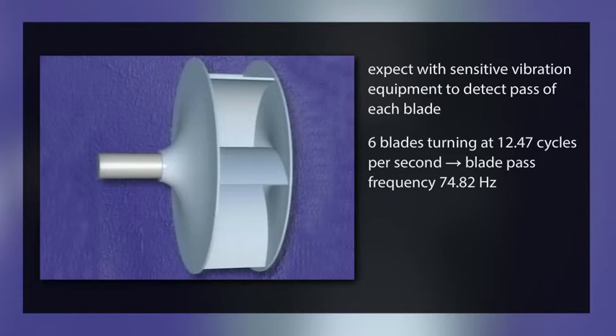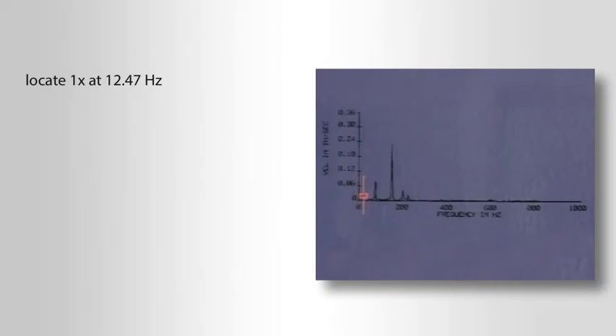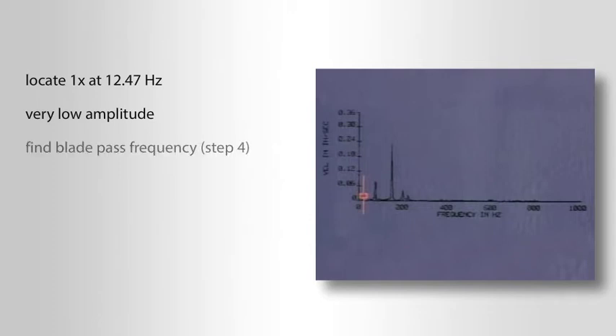The calculated blade pass frequency is 74.82 hertz. Here we see a vibration spectrum taken with no water flowing to the fan — step three. When we locate the one-times at 12.47 hertz, we find a very low amplitude.